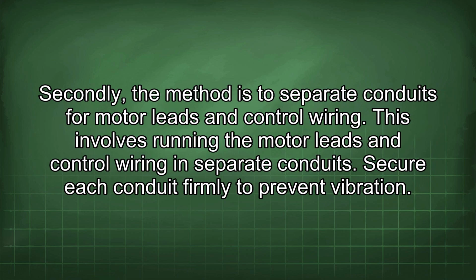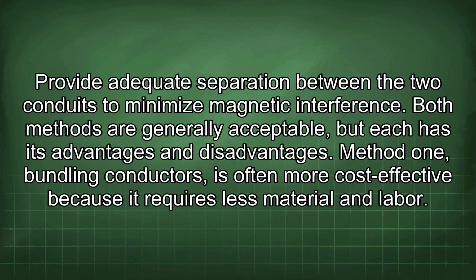Secondly, the method is to use separate conduits for motor leads and control wiring. This involves running the motor leads and control wiring in separate conduits. Secure each conduit firmly to prevent vibration. Provide adequate separation between the two conduits to minimize magnetic interference.